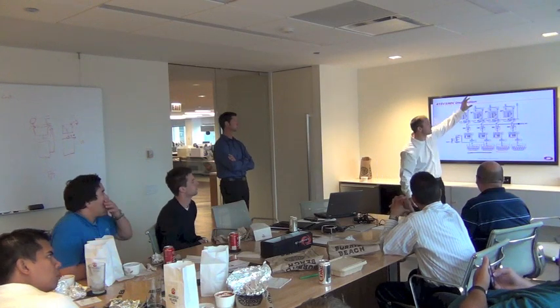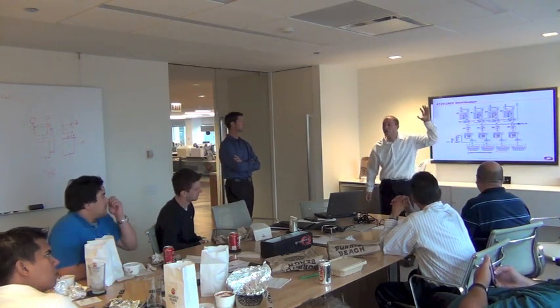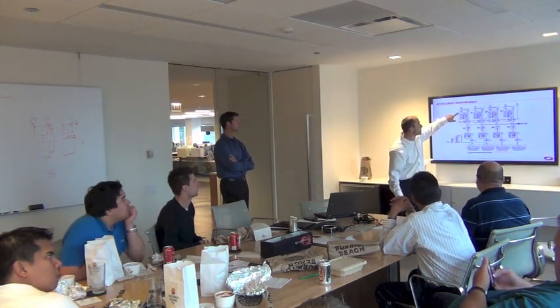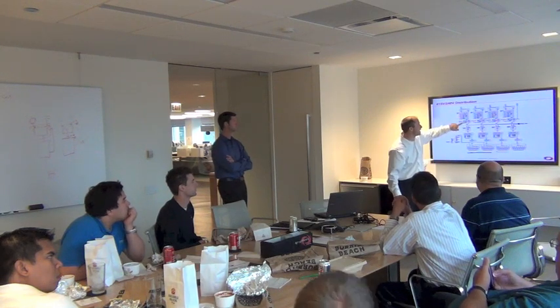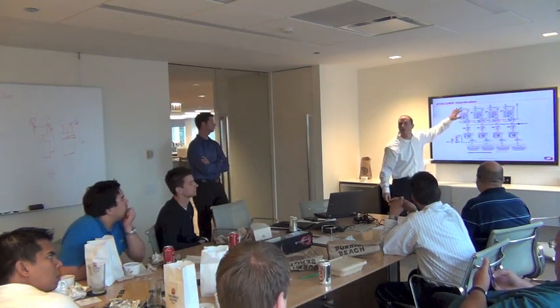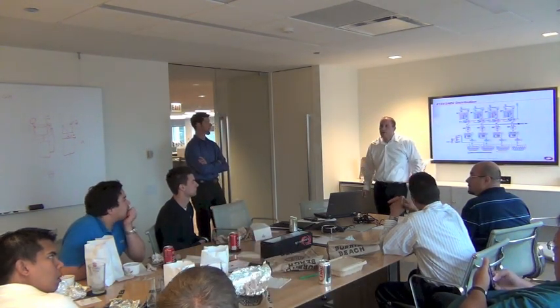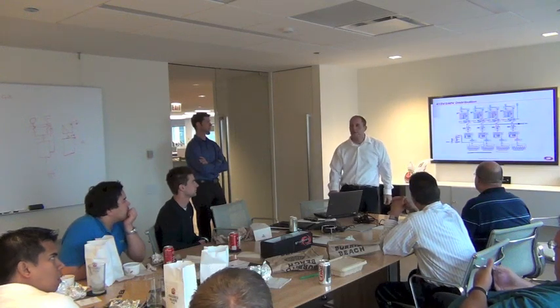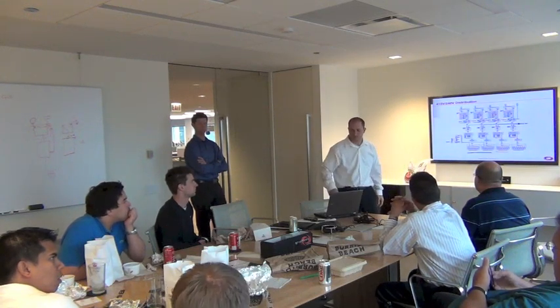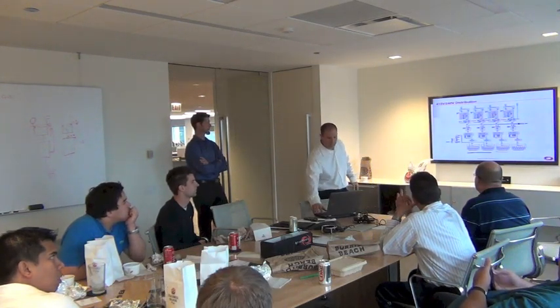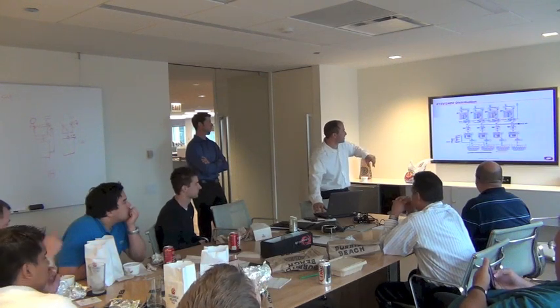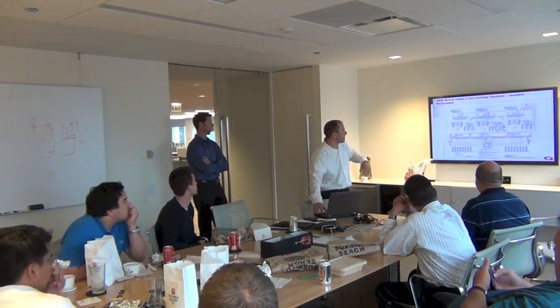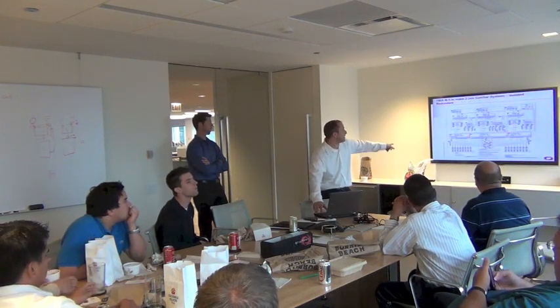but the generators are not in parallel. Even though the runs are all medium voltage, we basically integrate our UPS. This is basically like a medium voltage PDU. Are you guys going to run at 600 volts at all, or is it only 415? 415, 480. But this is a medium voltage installation that we did, and there's actually 4 phases of this. This is a big 3 to make 2 design via static transfer switches.